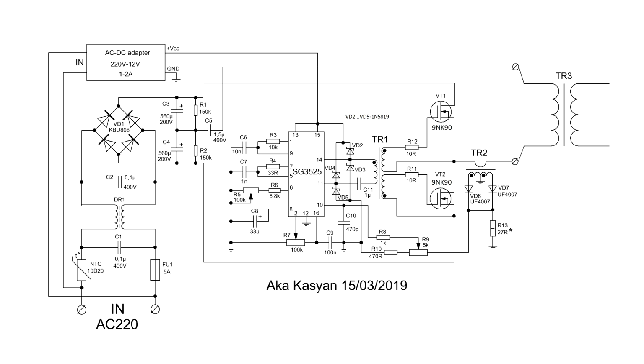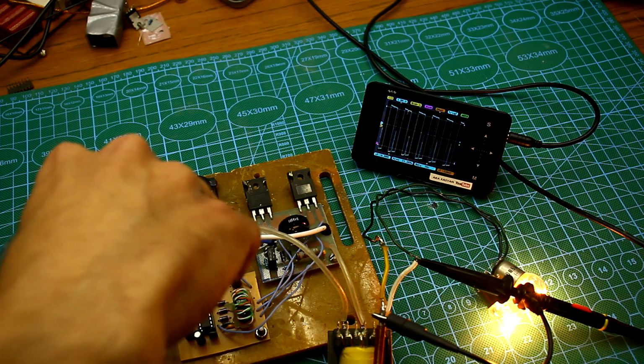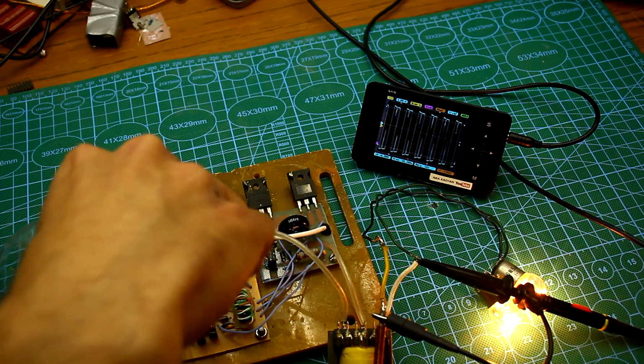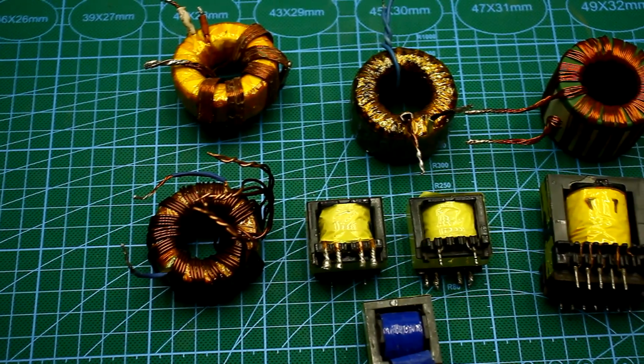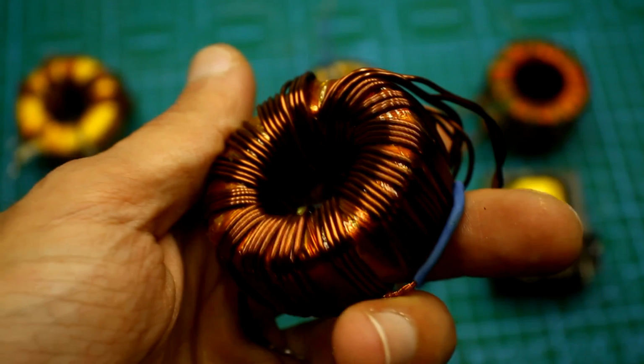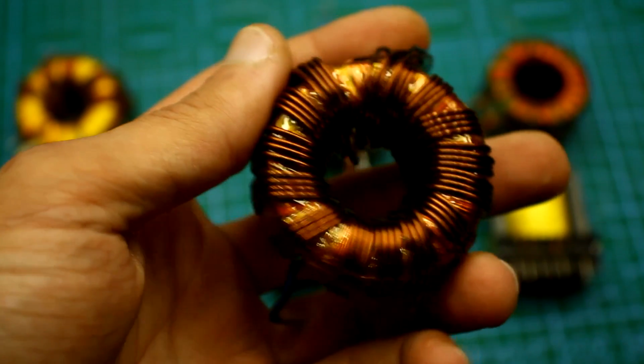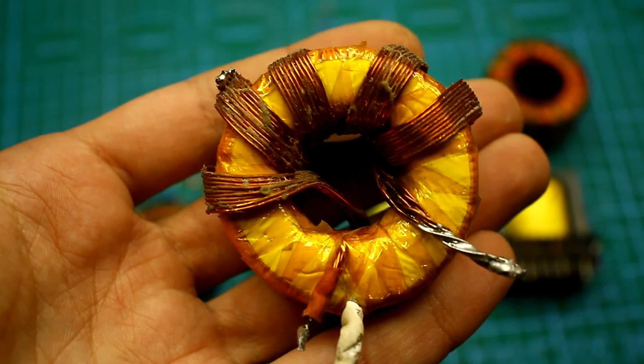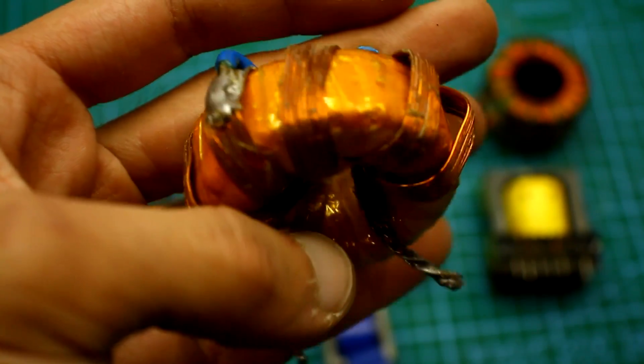And this is the full circuit of the test device for pulse transformers. The topology of the circuit is half bridge. As already said, there is a frequency control in the range from 13 to 205 kHz, because the transformers will operate in power units of different frequencies and our device must simulate the working conditions for any transformers.